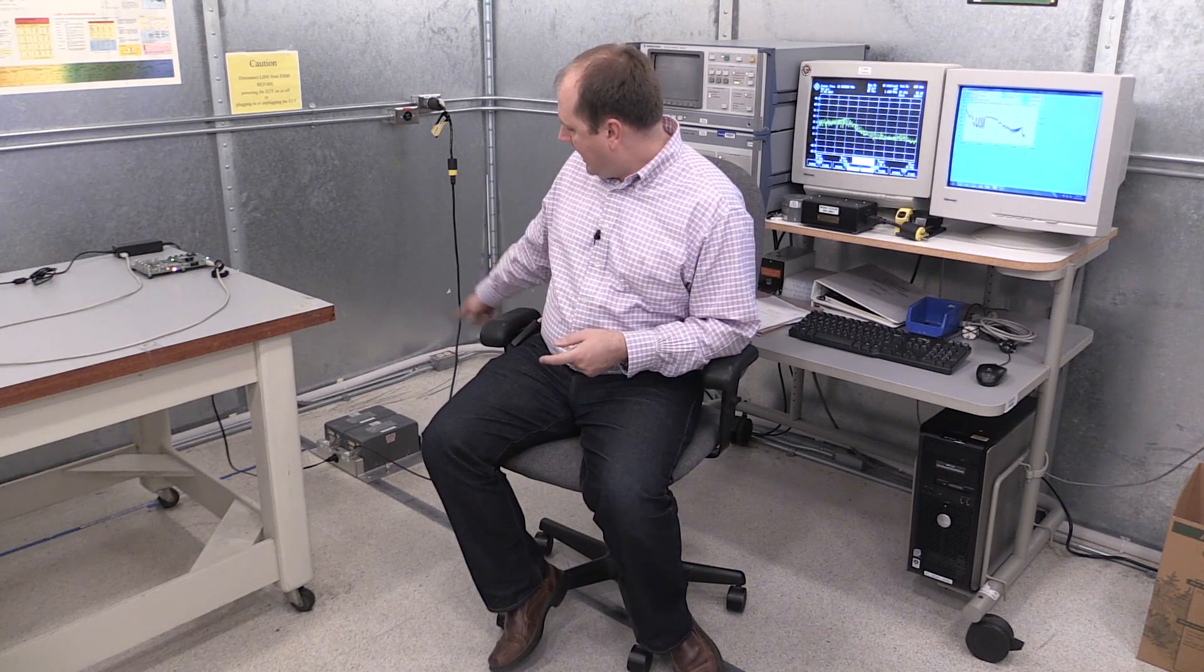Conducted emissions test means that I have my device under test plugged into power. So here I have an EMI receiver—it's doing conducted sweeps right now. The device under test is over on the table here and down on the floor there's something called a line impedance stabilization network.